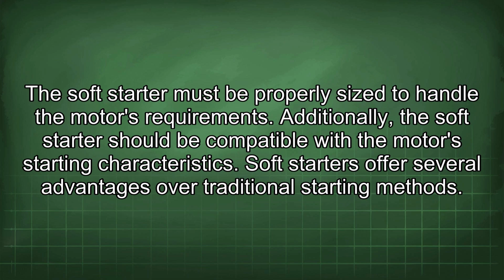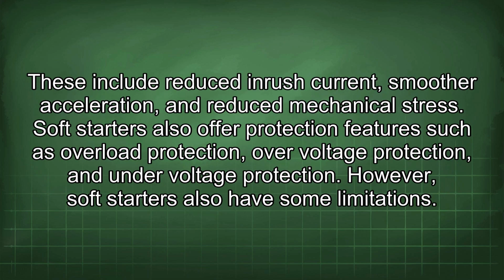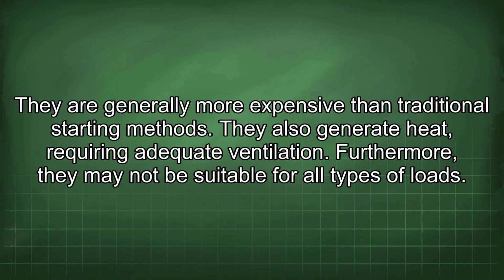Soft starters offer several advantages over traditional starting methods. These include reduced inrush current, smoother acceleration, and reduced mechanical stress. Soft starters also offer protection features such as overload protection, overvoltage protection, and undervoltage protection. However, soft starters also have some limitations. They are generally more expensive than traditional starting methods. They also generate heat, requiring adequate ventilation. Furthermore, they may not be suitable for all types of loads.